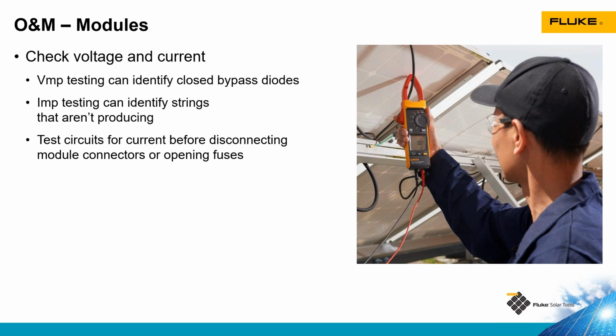I should also mention that we always use a non-contact current clamp to measure current in solar. If I am trying to measure current on my string of modules and I use a multimeter with the probe tips, as soon as I put the probe tips on the positive and negative, the meter is going to measure the current, assuming that it's below the current rating of the meter. But I've short-circuited that string through the multimeter. Once I remove the probe tips, that's under load and it's going to arc between the probe tips and the terminal that I'm measuring. It's going to cause damage and it's a safety hazard to the technician. So never measure current with the probe tips of a multimeter. Always use a non-contact current clamp.